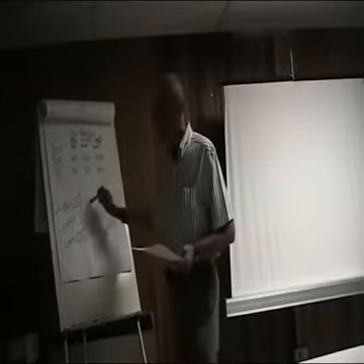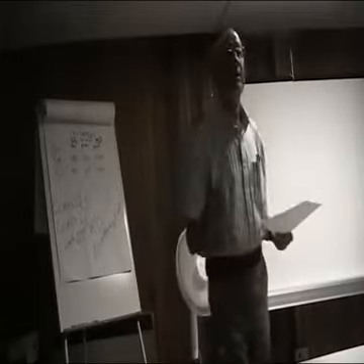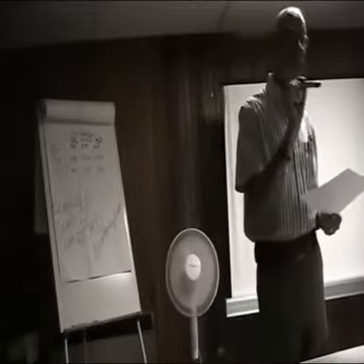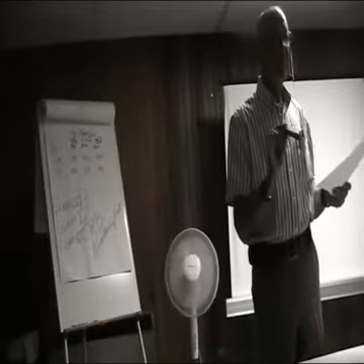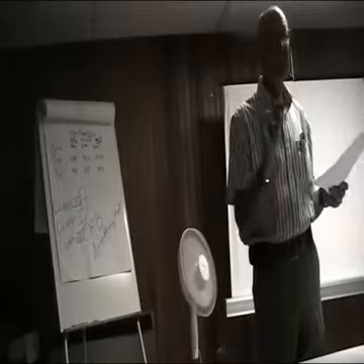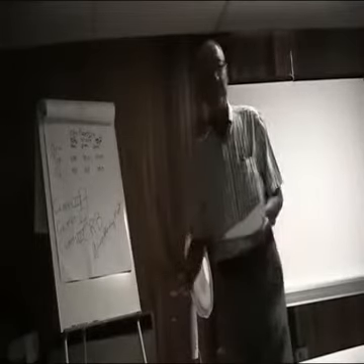The moment you see it's too high for a line class A, phone the guys and say, somebody made a mistake. Either the MFD is wrong, or my process data is wrong. Somewhere it doesn't tie up. A line class A cannot be a 600 pound. But you have to know that to fill it in.